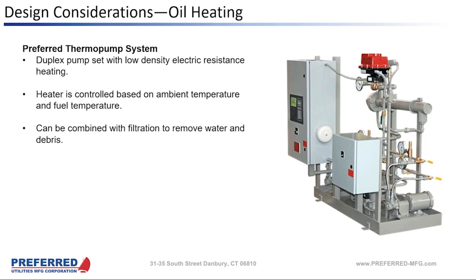So the heater does not necessarily kick on every time the pump runs. The heater's got its own local thermostat that'll kick in when the fuel actually gets cold. But sometimes all that's needed to take the edge off is to just circulate the fuel, maybe from the main tank through the building and then back, or whatever part of the system. And we can use control valves to really nail down what part of the system we're looking at. But overall, this is really the way to go, and the place that I start when I'm looking at a system where we're trying to make sure we're not going to have cold issues.